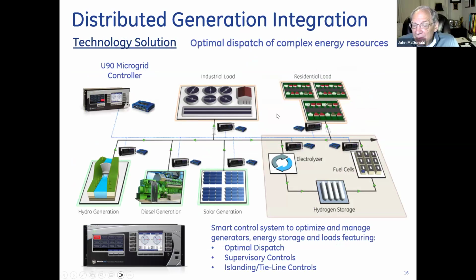So here's one. This was in a rural part of British Columbia in Canada. And you can see that this village, which is not near any utility, has residential load and industrial load. And they have hydrogen fuel cells, PV panels, hydro generation, and their base generation is diesel, which is pretty typical. The challenge is, though, the diesel is expensive. To get the fuel to a rural area is expensive. But also when the diesel generator operates, it sends carbon dioxide to the atmosphere, right? So what we want to do is minimize the use of the diesel and maximize the use of the other resources. And we do that with, in the upper left here, we have the microgrid controller.